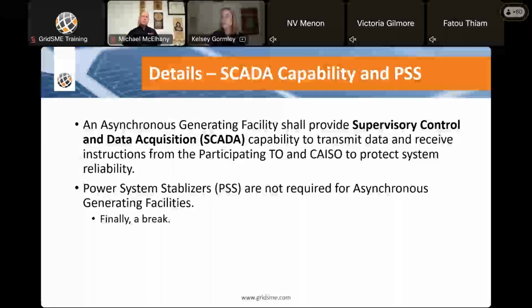All right, we'll talk a little bit about SCADA capability and power system stabilizers. So an asynchronous generating facility needs to provide supervisory control and data acquisition, SCADA, capability to transmit data and receive instructions from the PTO and CAISO to protect system reliability. With CAISO, that's the CAISO rig, and with the utility, that's typically via the RTU. So the participating transmission owner and CAISO and the asynchronous generating facility shall determine what SCADA information is essential for the proposed asynchronous generating facility, taking into account the size of the plant and its characteristics, location, importance in maintaining generation resource adequacy, and transmission system reliability. So this can be specific to your interconnection. This isn't just a generic out of the box. This can be specific to your interconnection as well.